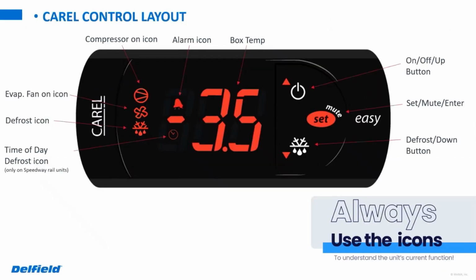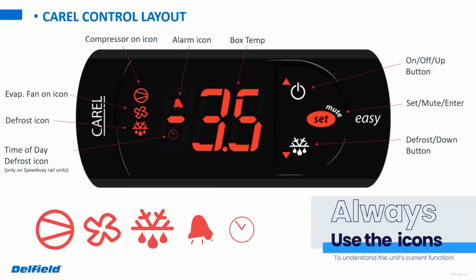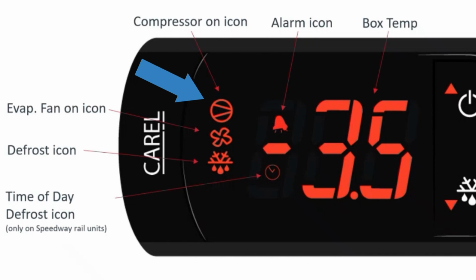The big thing with this control, you want to make sure that you're paying attention to the icons outside of the control. So we will be looking at the temperature on that, obviously, but again, the big thing is going to be the compressor icon, the fan icon, if it's in defrost or not, if there's any alarms showing on there. So we want to make sure that when we're going through this control that we're paying attention to those icons outside of it there.